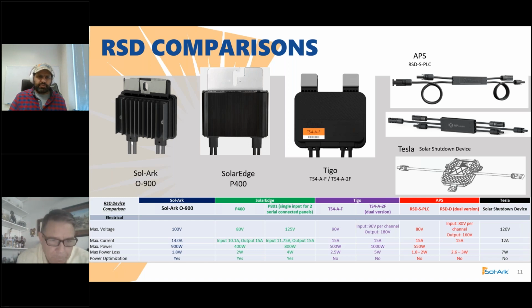So you've got the Solar Edge. It's sort of similar to Solar Edge, except that it actually works. The Solar Edge optimizer does not work with the Sol-Ark. It only accepts a signal from a Solar Edge inverter. If you take a Solar Edge inverter out of a system and neglect to remove the Solar Edge optimizers on the panels, then connect those panels to the Sol-Ark, there's a high likelihood it will not work. So Solar Edge kind of locks you into just their product, and has a pretty decent failure rate, but we have our own in-house solution because people may want that rather than going to a third party.